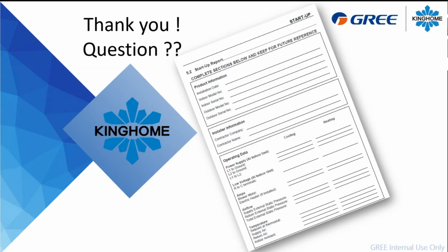Before, in the red, it said that you have to preheat it for 8 hours. Is there anything in the warranty where it's going to void it if it wasn't run for 8 hours? Because it's not going to be run or heated up for 8 hours. No, it will not, but it's highly suggested to just make it warm before you start it. The manufacturer says 8 hours to avoid any kind of problem. If it's like minus 30 outside, maybe it will take you a couple of hours for the compressor to be warm enough for the startup.